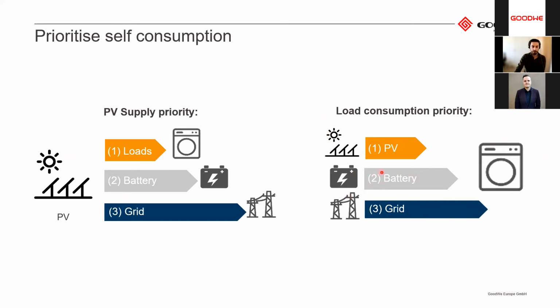But there are also different ways to set it up. So you can force charge the battery or force discharge the battery during specific times of use. So you can set it up to charge the battery between maybe 2 in the night and 6 in the morning. And then between 7 in the morning and 10, you discharge the battery.